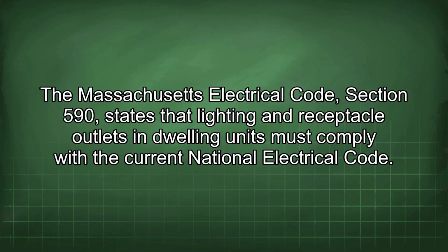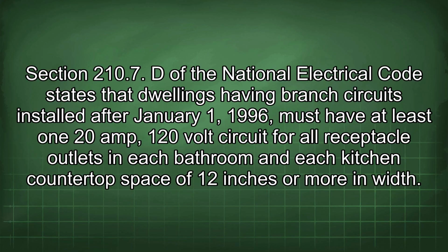The Massachusetts Electrical Code, Section 590, states that lighting and receptacle outlets in dwelling units must comply with the current National Electrical Code. Section 210.7(D) of the National Electrical Code states that dwellings having branch circuits installed after January 1, 1996 must have at least a 20 amp, 120 volt circuit for all receptacle outlets in each bathroom and each kitchen countertop space of 12 inches or more in width.